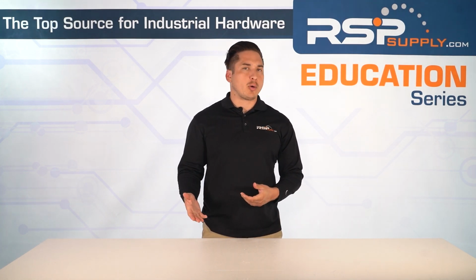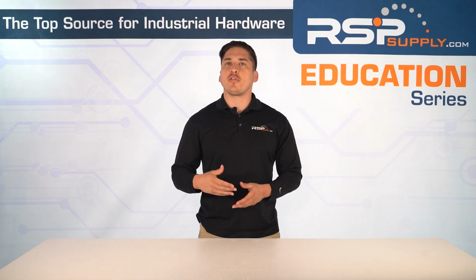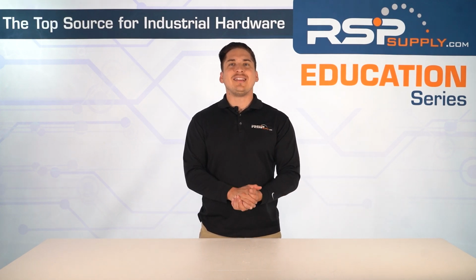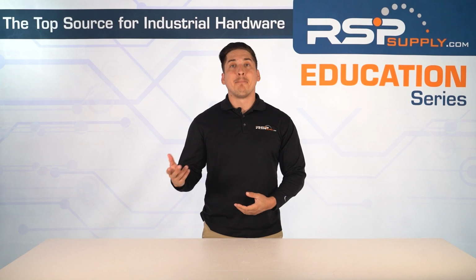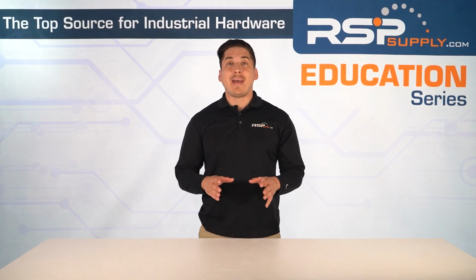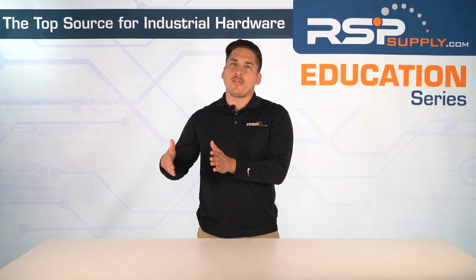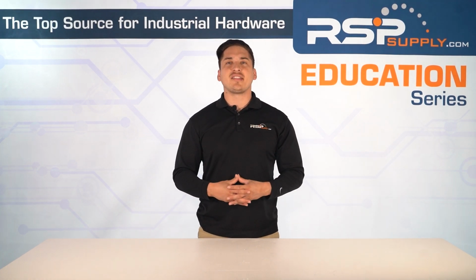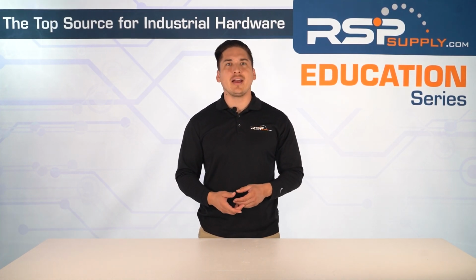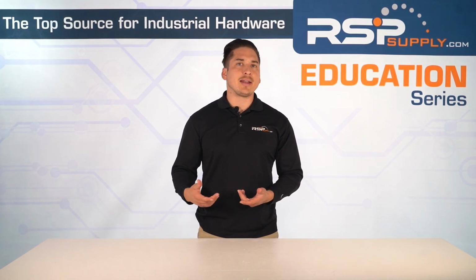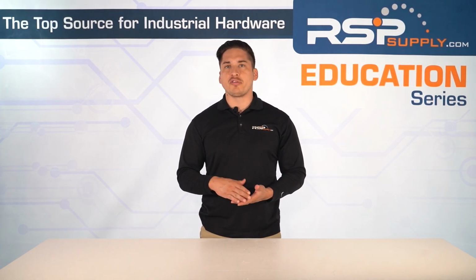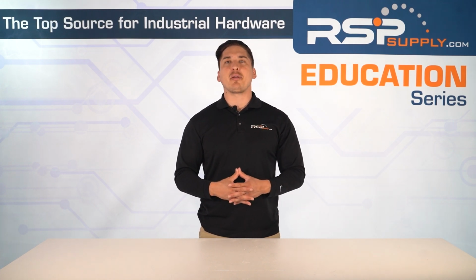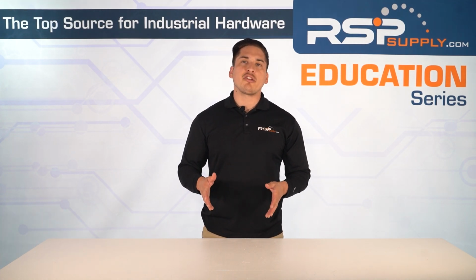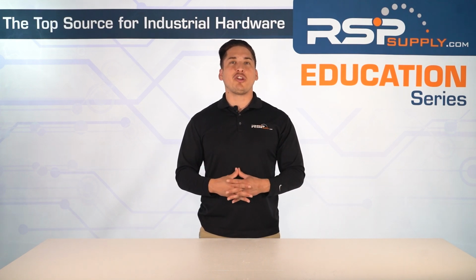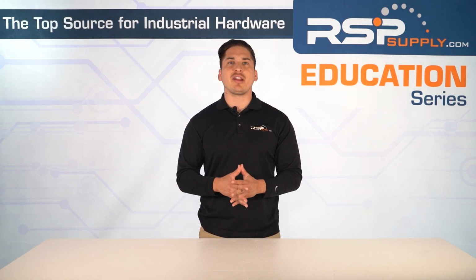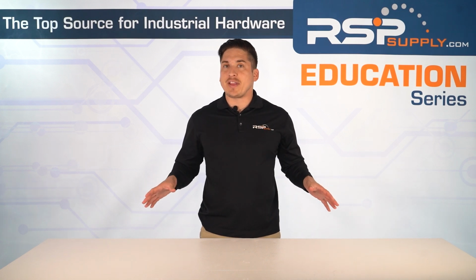So a quick recap. Motors, go horsepower rated. HVAC systems, consider the full mix of components. Solar, DC rated or nothing. Lighting, ballasts and drivers change the game. Match voltage and current, plus give yourself a bit of a margin. Always check the SCCR or the short circuit current rating and environmental ratings, NEMA and IP. And don't forget to count your poles and throws. Now you've got the roadmap to pick the right disconnect every time. No guesswork, no regrets. Thanks for watching. And remember, the right disconnect switch doesn't just complete a circuit, it protects everything behind it.